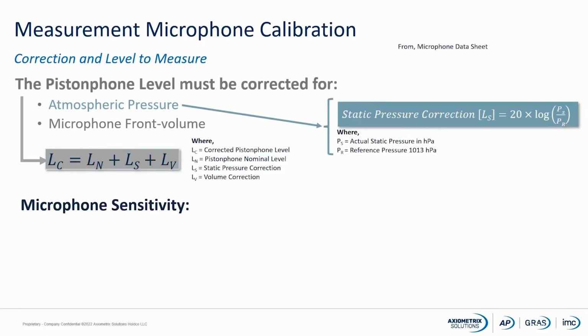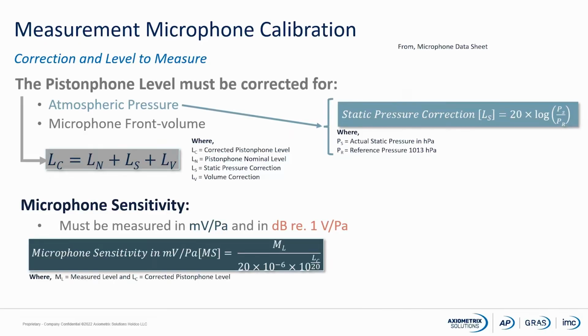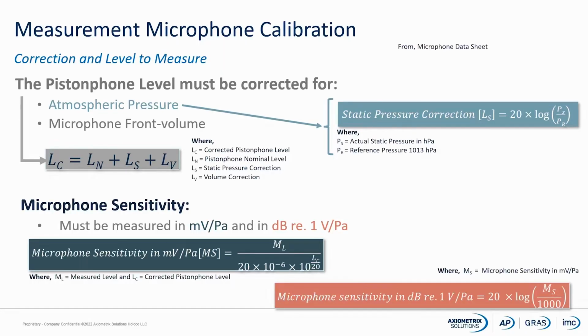When we measure the microphone sensitivity, then it must actually be measured in millivolt per Pascal, and also in dB relative to 1 volt per Pascal. Normally we are measuring in millivolt, so we can calculate the sensitivity directly in millivolt, and we can also do the calculations into dB re 1 volt per Pascal. So we need to have both values on the calibration chart.